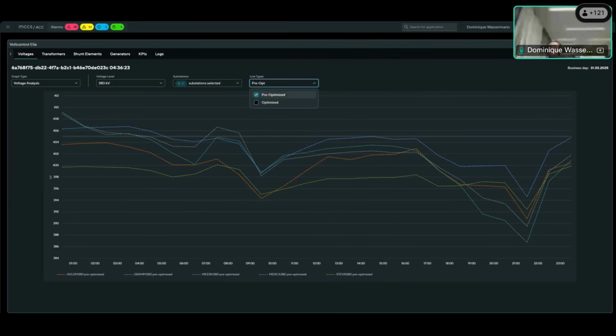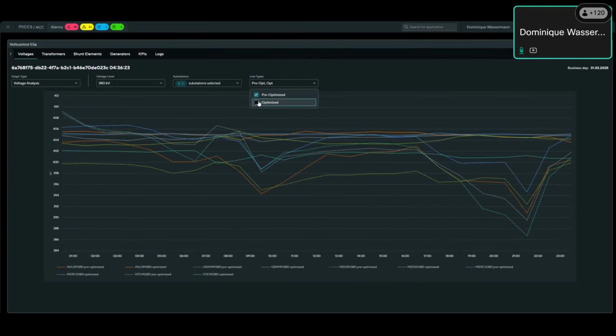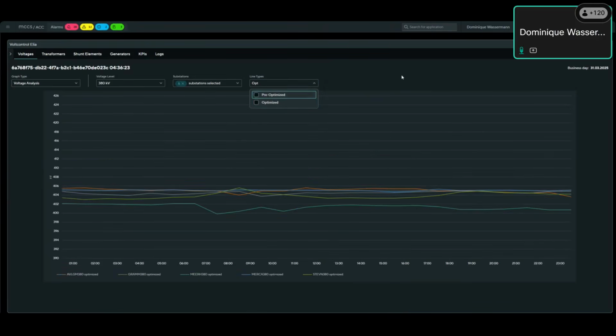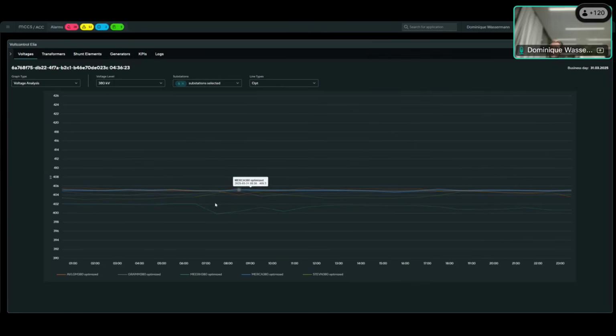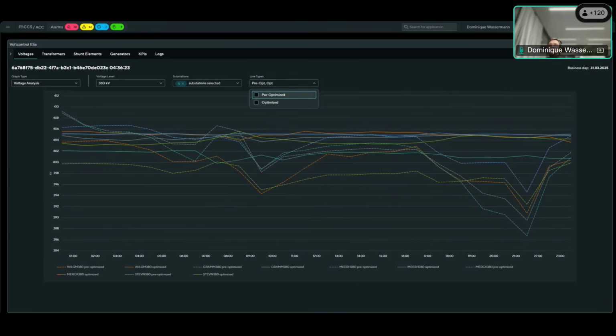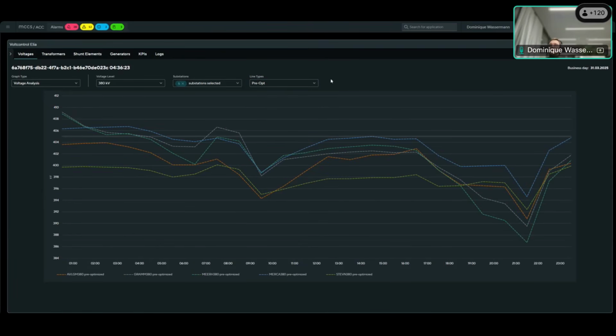Now, if we turn on the optimized values of these substations, the voltage curves, you can see that we are much closer, first of all much flatter, but also much closer to our target voltage of 405 kilovolt. So in short, our optimization has done what it should. We want to be close to the target voltage, and we have decreased the volatility of our voltages in the grid.